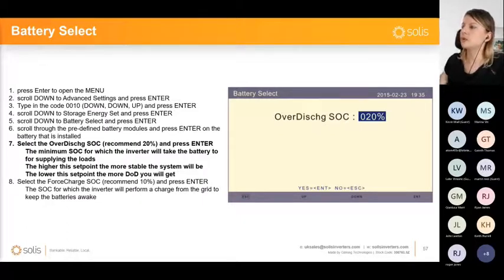This is something that we need to set, and we usually recommend it to be at 20%, especially during the winter times. If the batteries would start discharging below this percentage, then at some point it can be 1 or 2 days without PV output. That SOC will drop more and more, and at some point it's going to reach the point where the battery will just turn off, and it will not automatically reconnect when the PV gets back. So it's best to give some room.